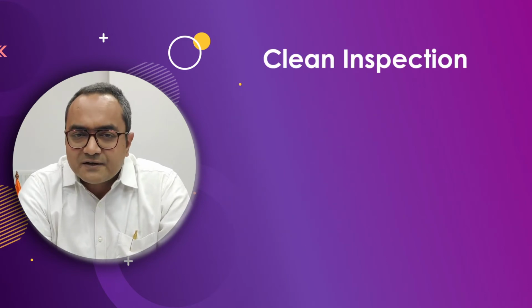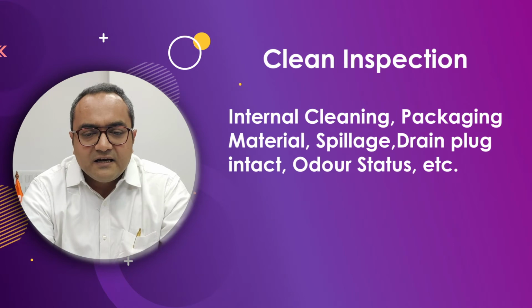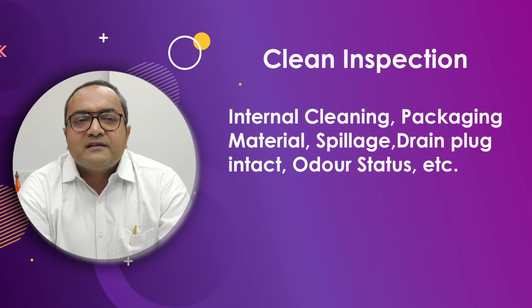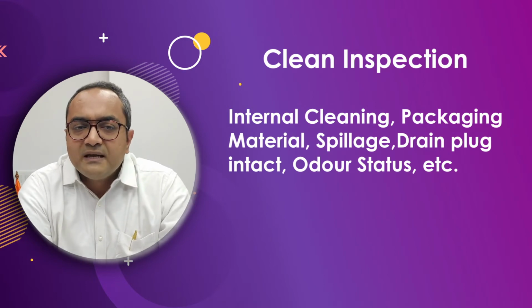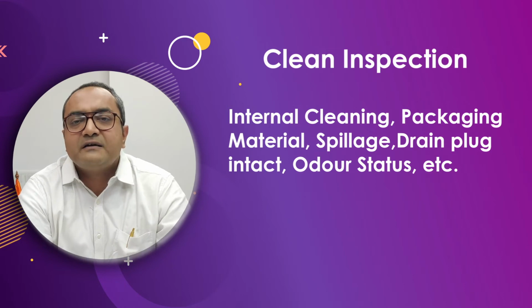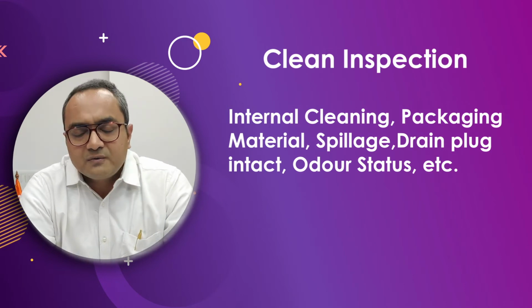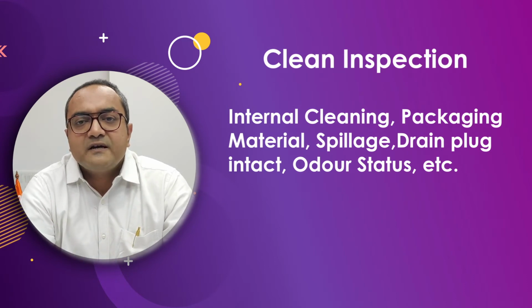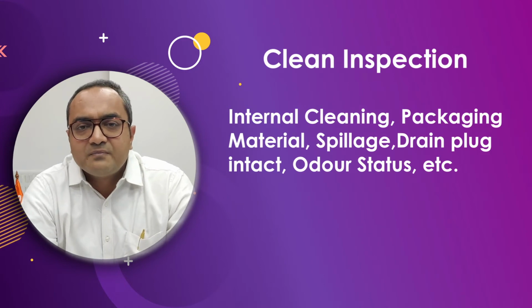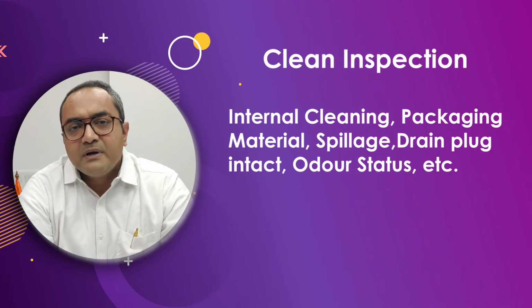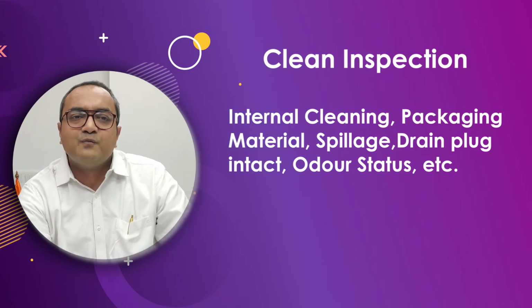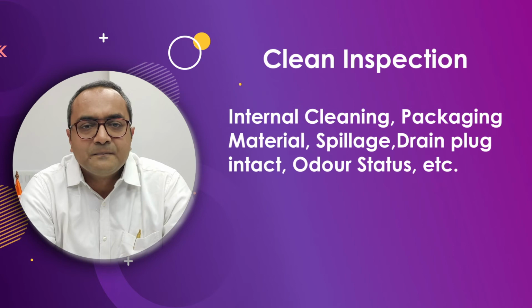The second is clean inspection, which is basically the indoor container inspection. It is carried out for internal cleaning, packaging material, any spillover or spillage, or whether the drainage plug is intact, because the reefer container has the vent facility as well. So for inflow and outflow, the vents are also available. The vent has to be checked properly, whether they are operating properly or not, any odor, any drain plug issues. That is basically the power off mode or non-supply mode inspection.